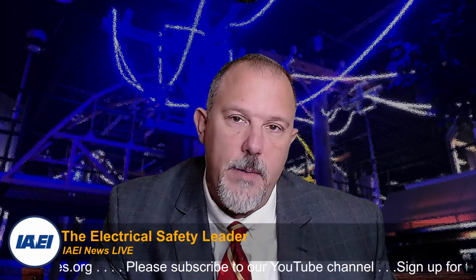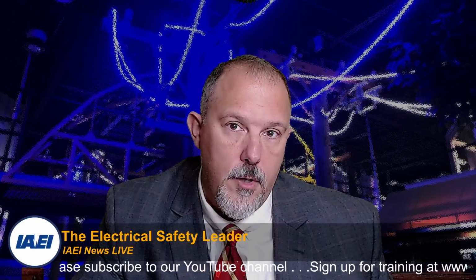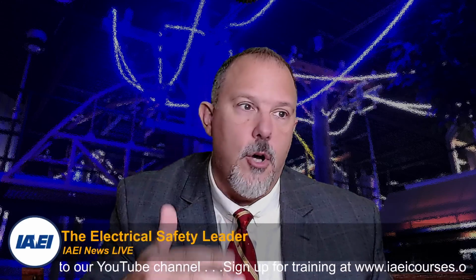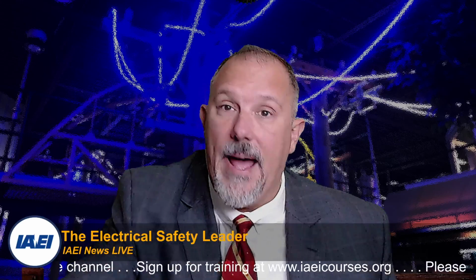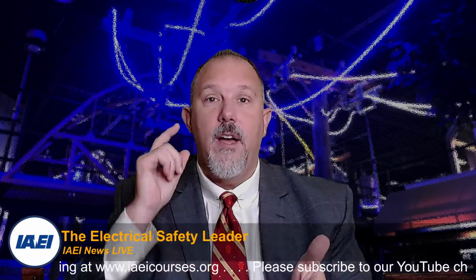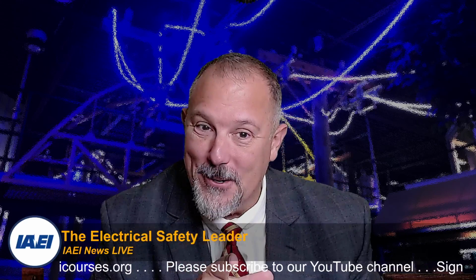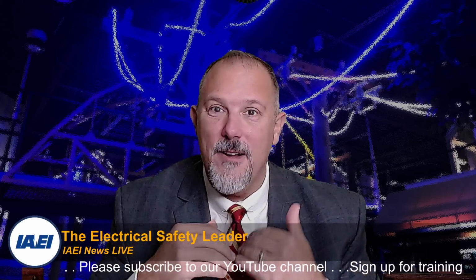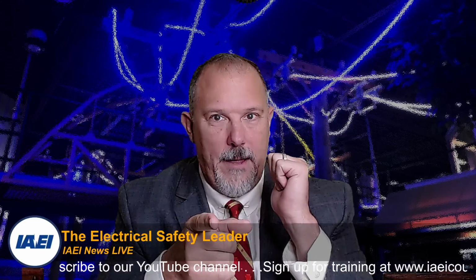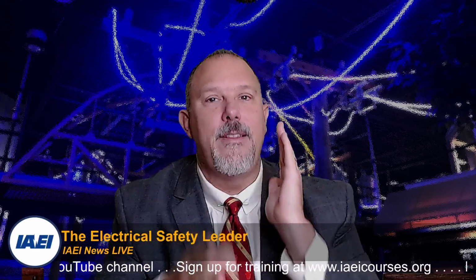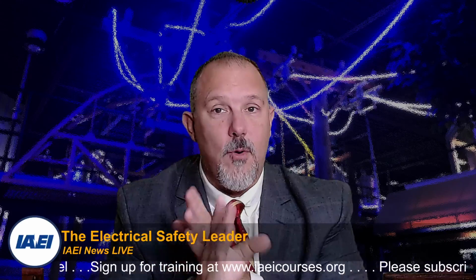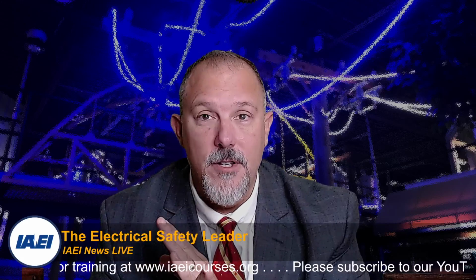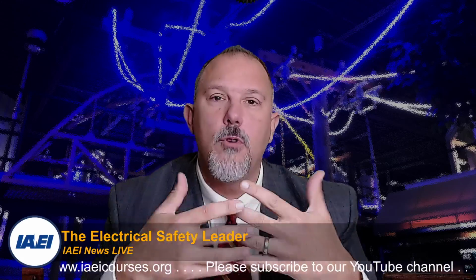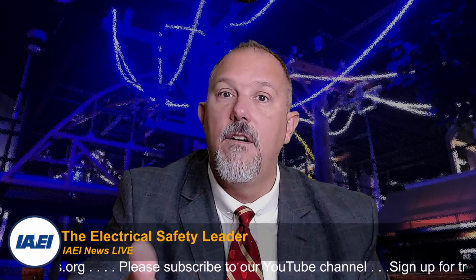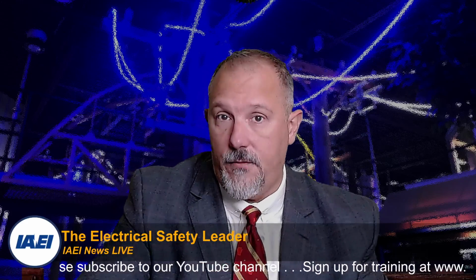The major difference between a short circuit and an overload is that an overload current stays in the path. Look at it that way. It's like you have a two-lane highway. You have the right side of the road, depends upon what country you're in, but the right side of the road where I'm from goes this way, and the left side goes this way. As long as all the cars stay in their lanes, if I have too many cars in one lane, I can have an overload. So if I pull current in excess of the ampacity of a conductor based upon the conditions of use, it's an overload.